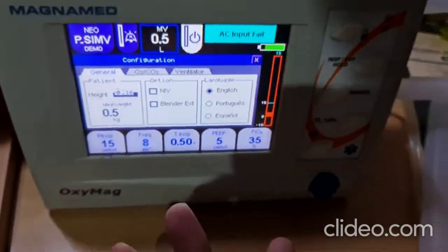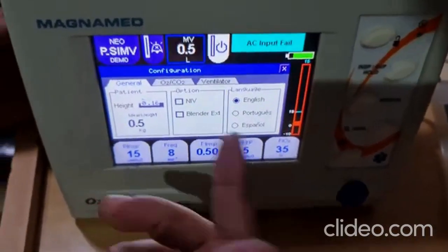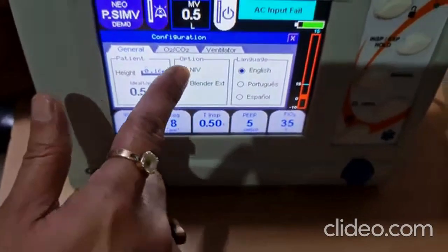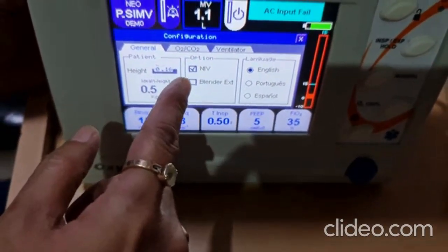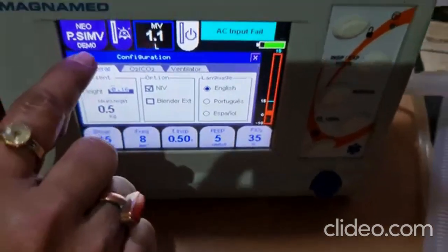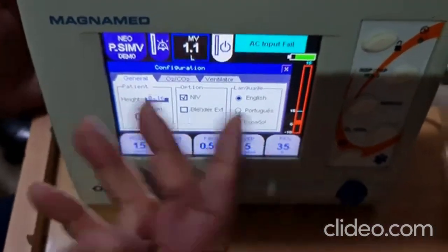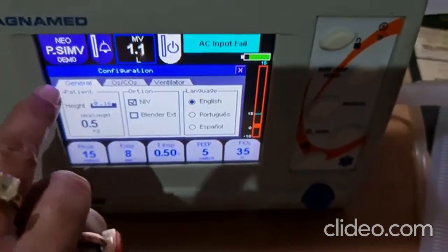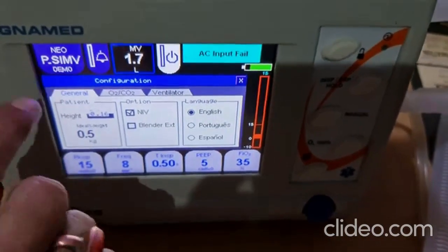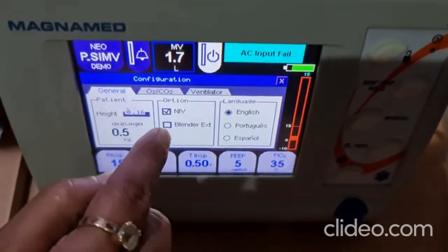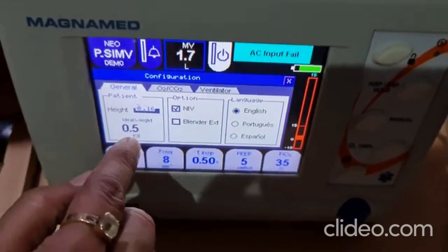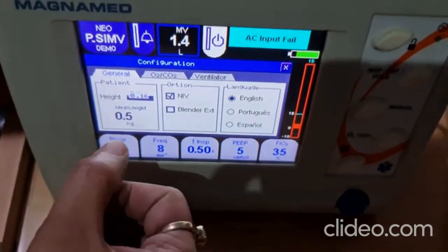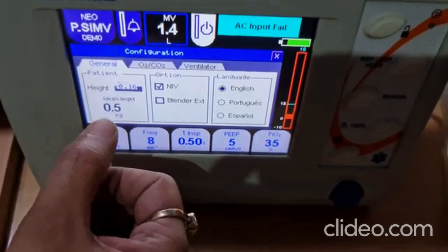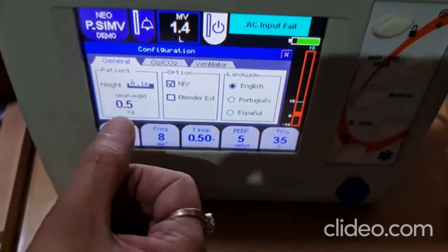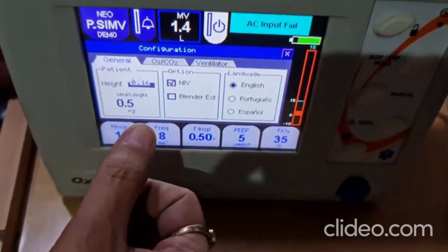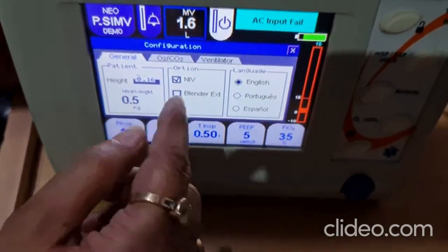It has a NIV ventilation also. If you want to use any mask or cannula or something, you can select the NIV. In the demo mode, it is not showing NIV. If you connect it with the gas, you will not use the demo mode. It will show you NIV here. When you select the NIV here, unselect. So it can be used for neonatals. It can start from half kgs. It's a very good machine, maintenance free machines.